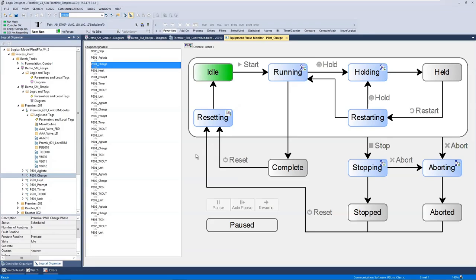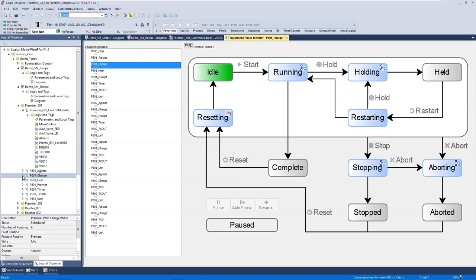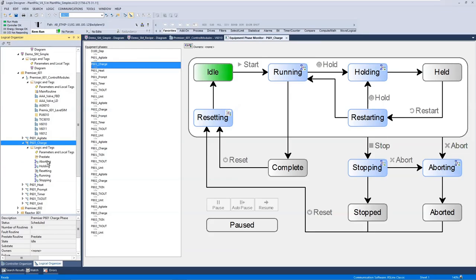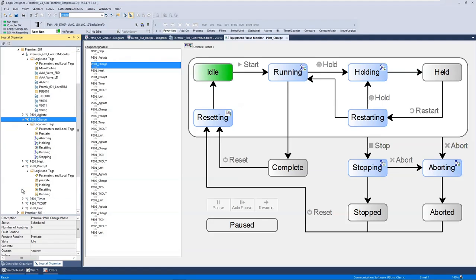What you have to worry about in your Phase Manager is which steps you want to support. So do I have a running step? Do I have a holding step? And then what do I need to do when I'm in them? So in our example here, we have our charge equipment phase, and this has the aborting, holding, resetting, running, and stopping state. But if we go and look at our prompt state, it only has holding, resetting, and running. It didn't need the aborting step.